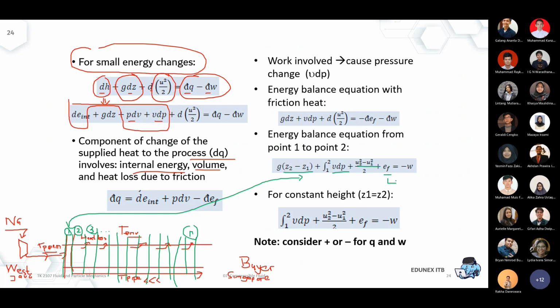And if you remember EF, again you use the fanning factor that was taught previously. It's still applied, but only accurate enough for a relatively small pipeline length. Because when you try to force it to be applied for the overall length of your pipeline, maybe your density, your meter per second, already changes.